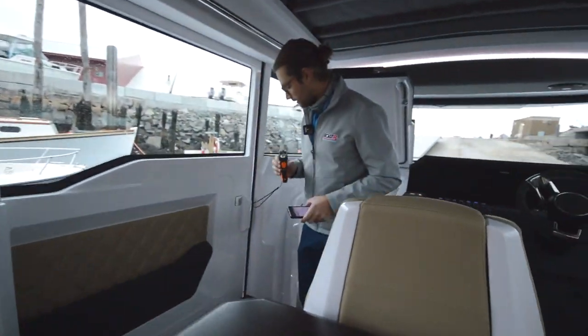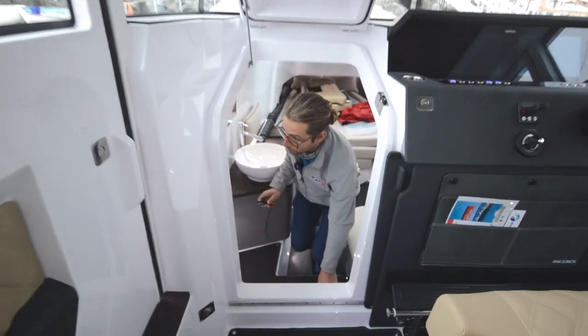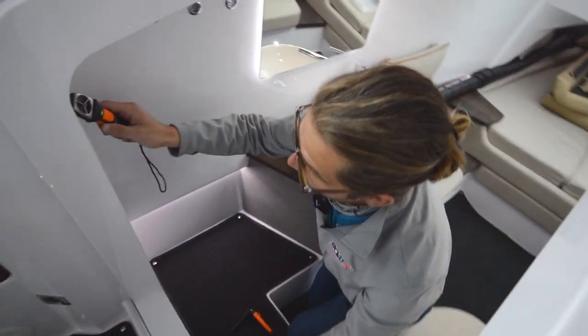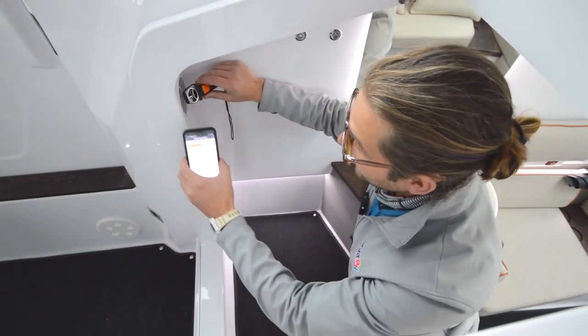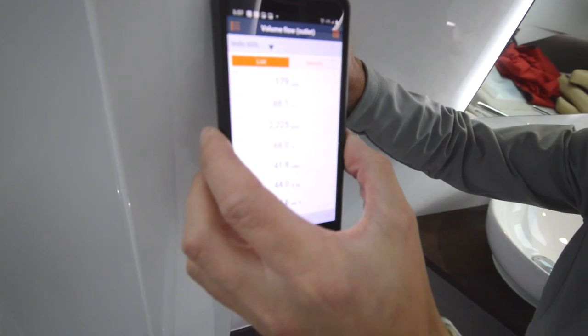I'm going to take this little handheld anemometer and hold it up to the supply grill for that 7000 BTU unit. In doing so, I'm going to try and find the sweet spot where it moves the fastest. You're going to see that you get a little over 180 CFMs.